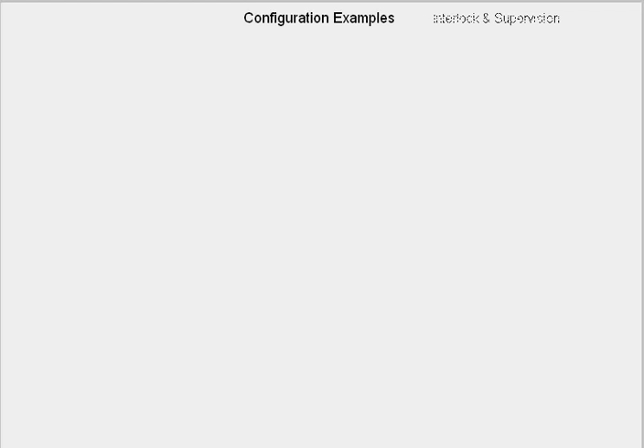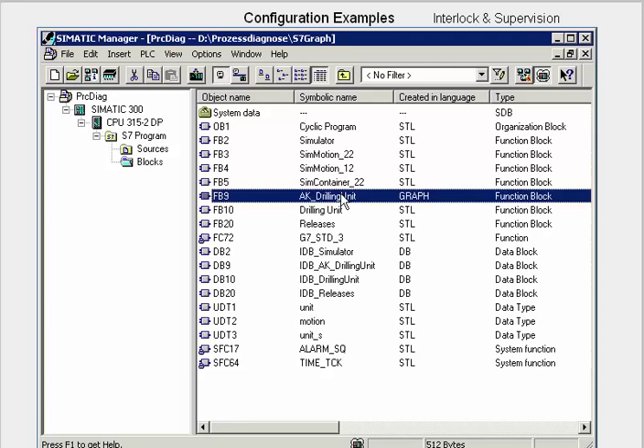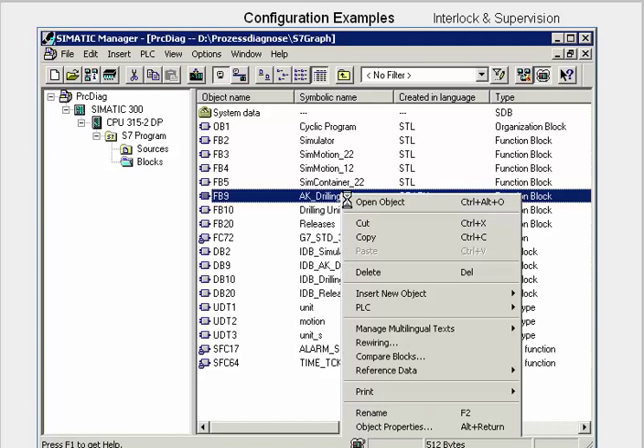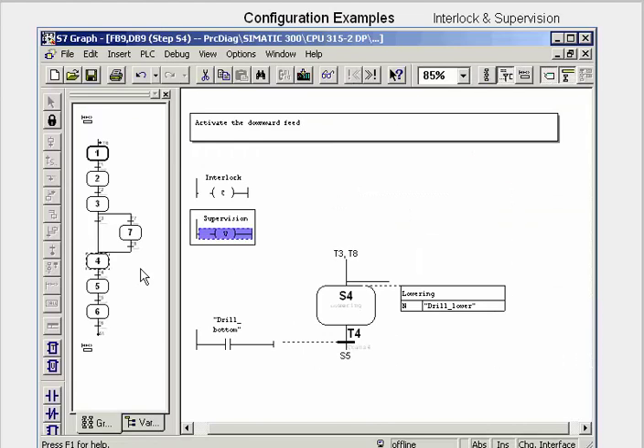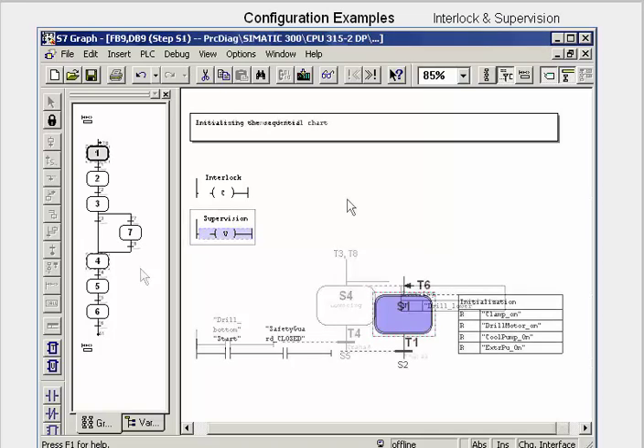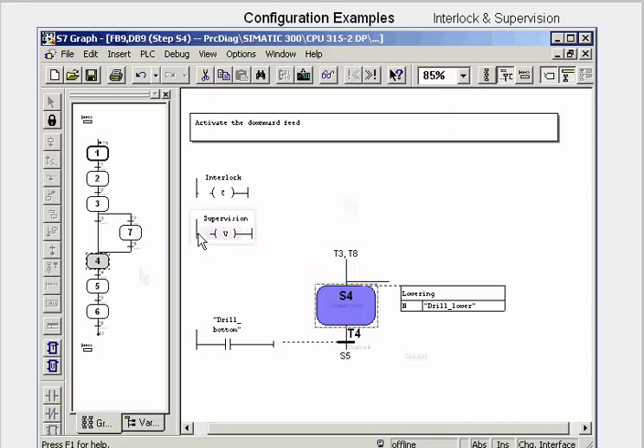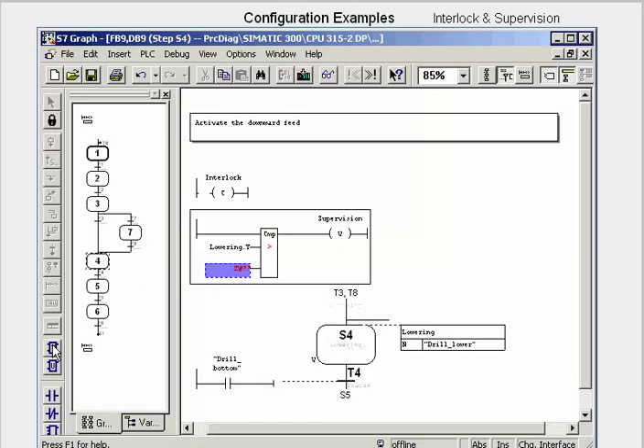The following example deals with the configuration of interlock monitoring and supervision monitoring in the S7 graph language. We open the block that contains the sequencer. A supervision means that a message is triggered when the step concerned is not completed within a certain time; depending on the global settings, the active step is then closed. We select step 4 and insert in the wildcard for a supervision a comparator as time monitor parameterized with a monitoring time of 5 seconds.